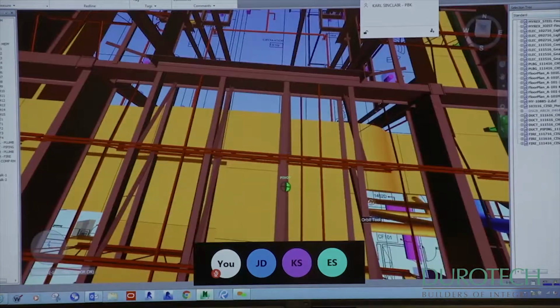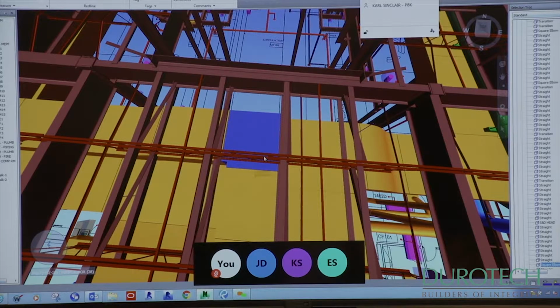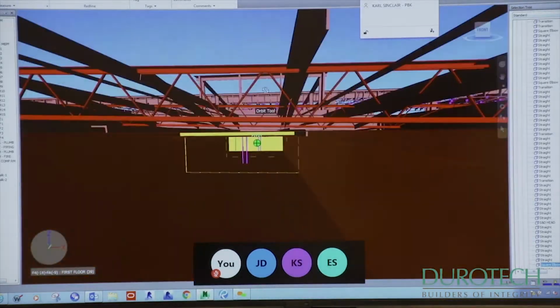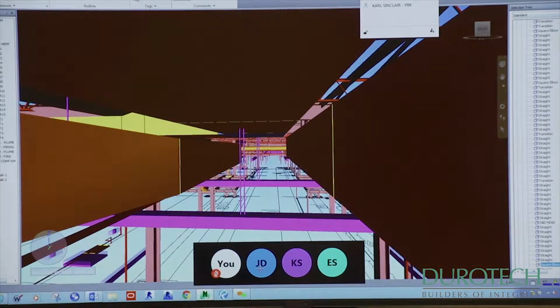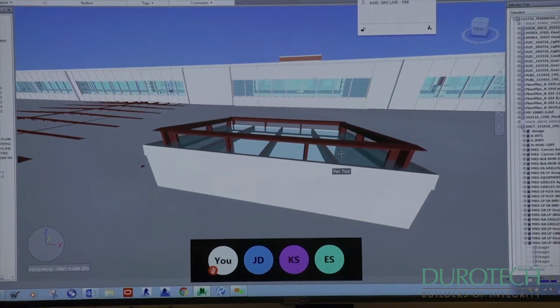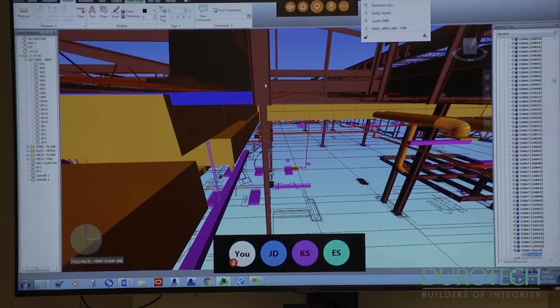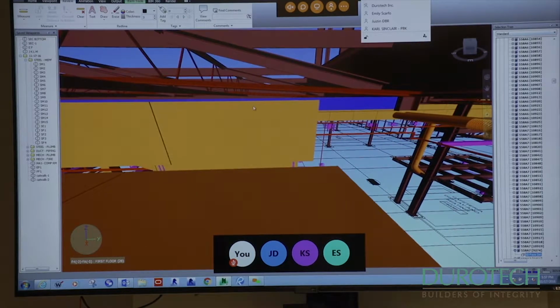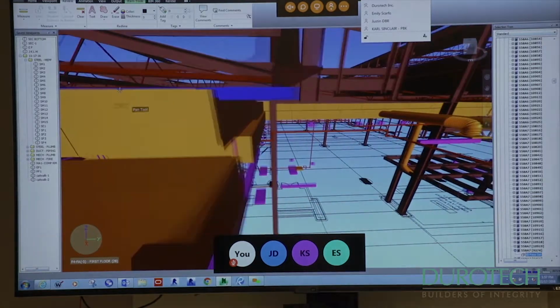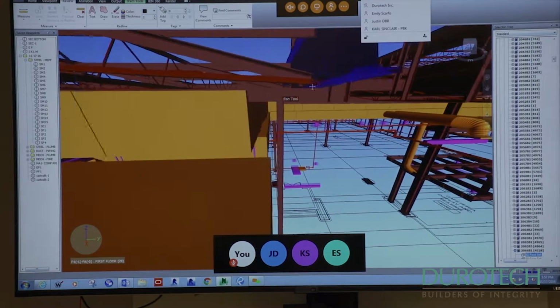My only concern was that they are continuous bridging and all of them are hitting the duct here. Looks like the bracing holding the angle for the masonry above it. Everywhere we have that low high, we've got that condition with all that angle. So you've got a double back-to-back angle on the roof side for the masonry. Actually, what beam you have, and then you've got a back-to-back angle sitting on top, sitting outside and up. Yes, and that's the one which is connected. I think it's welded or connected to this bottom chord.